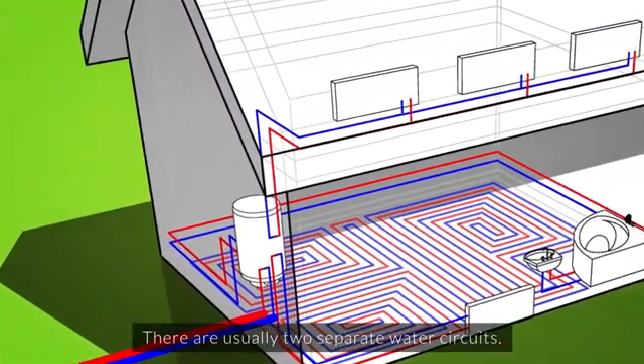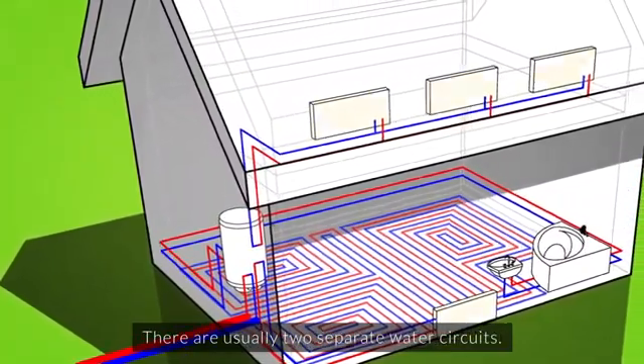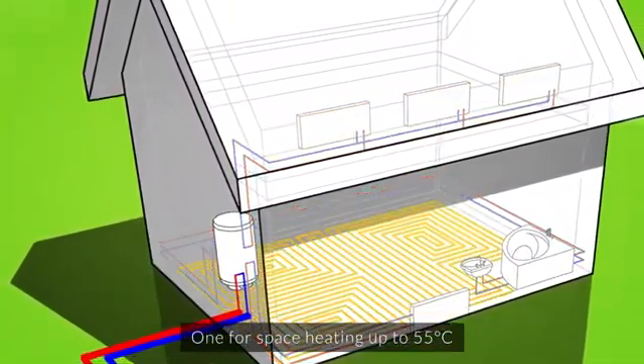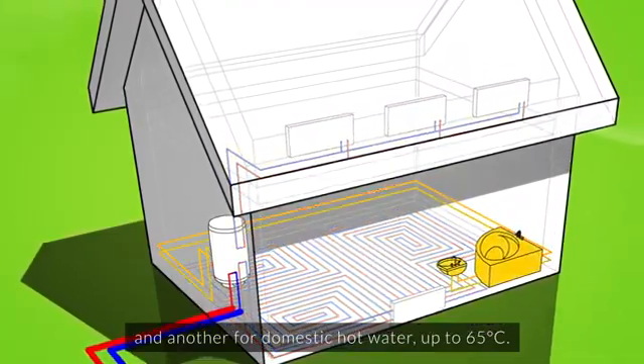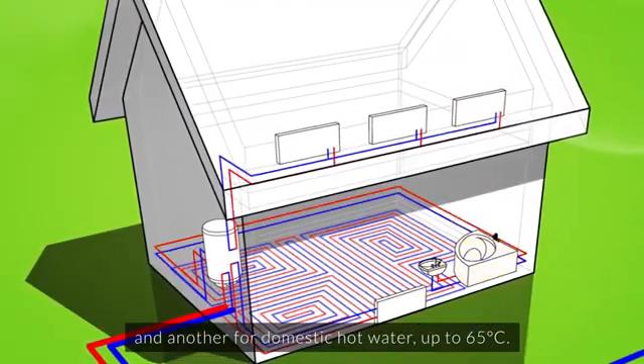There are usually two separate water circuits: one for space heating up to 55 degrees Celsius and another for domestic hot water up to 65 degrees Celsius.